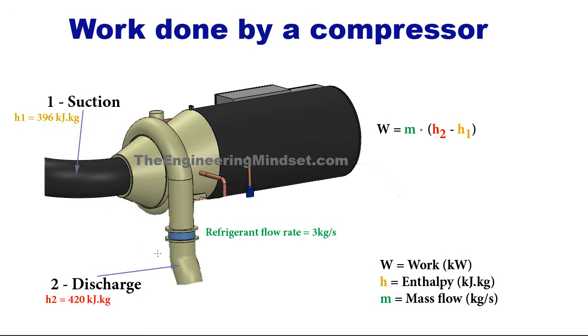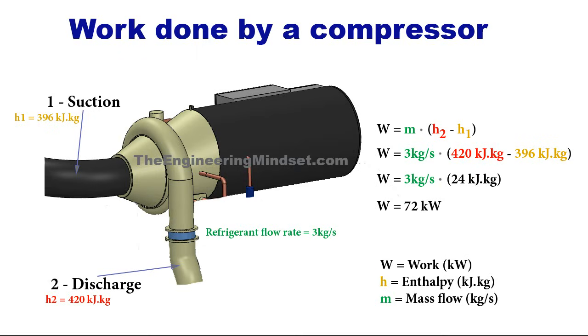So for every kilogram going in, remember there's 3 kilograms there, that means there's 396 kilojoules going in, and there's 420 kilojoules per kilogram coming out. So it's much more densely packed. The enthalpy has been compressed in there. So we can calculate that, so we can fill in the numbers, and work equals 3 kilograms per second times 420 kilojoules per kilogram minus 396 kilojoules per kilogram. That leads us to 3 kilograms per second multiplied by 24. That's the difference in these two, and that results in the work being done as 72 kilowatts.